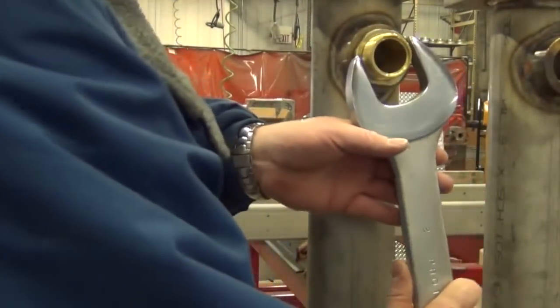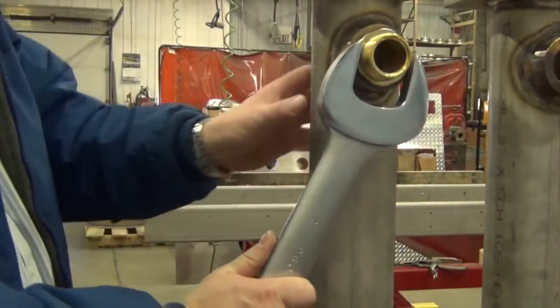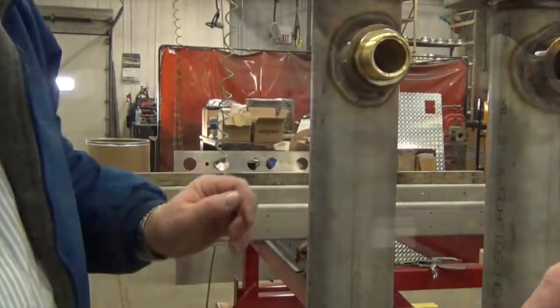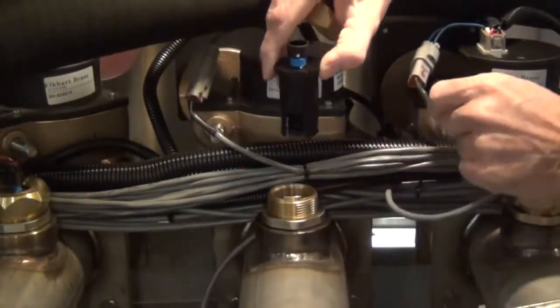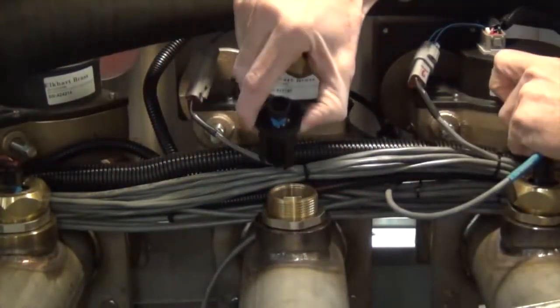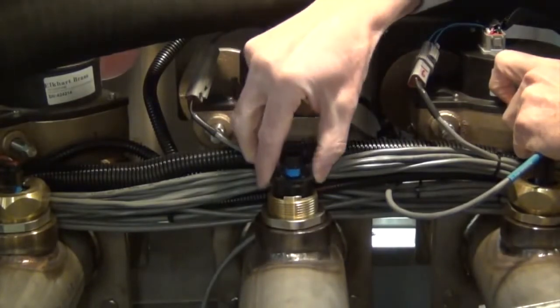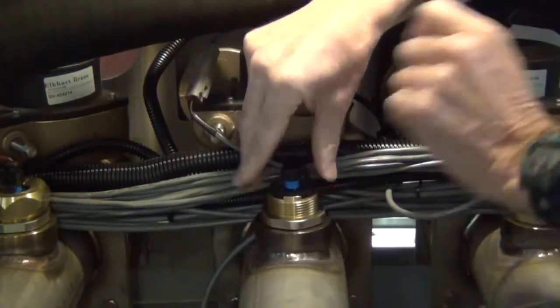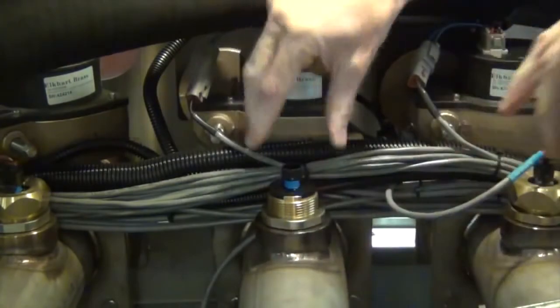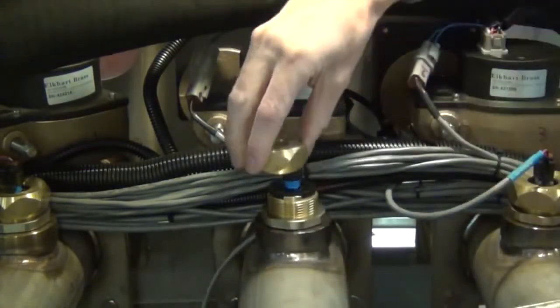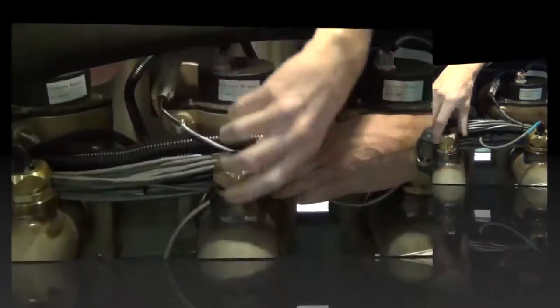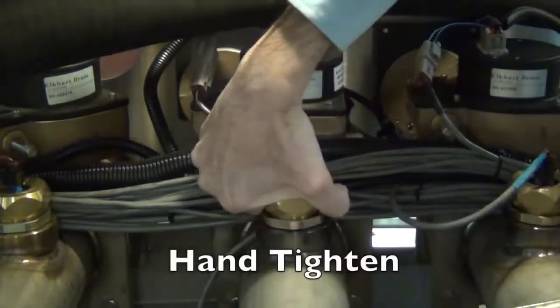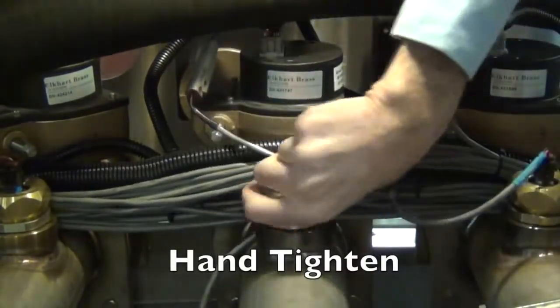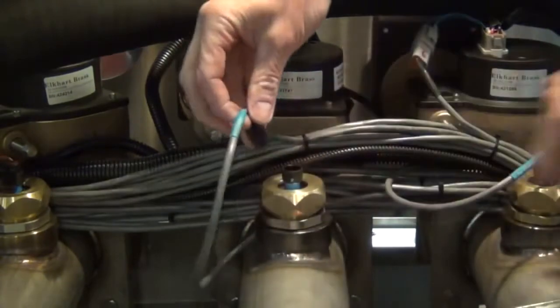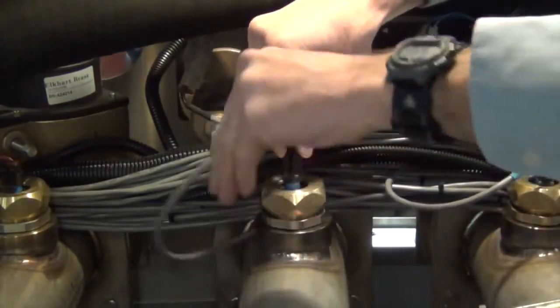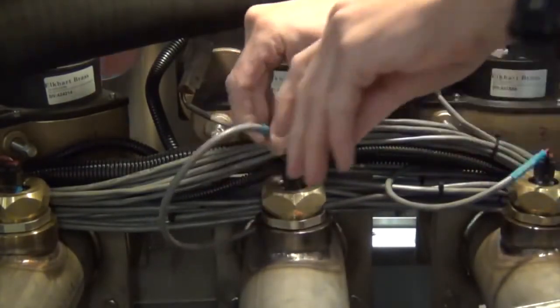Tighten the locking nut with medium torque. When installing the flow sensor, align the flat section of the sensor rim with the alignment tab. Make sure the O-ring is in the sensor housing groove. Hand tighten the retainer cap. Connect the flow sensor with the included cable.